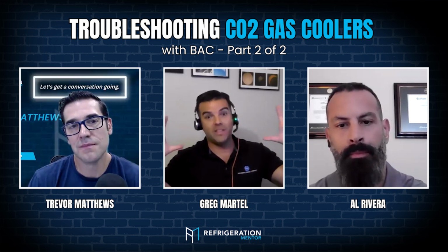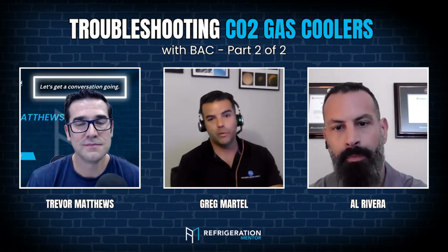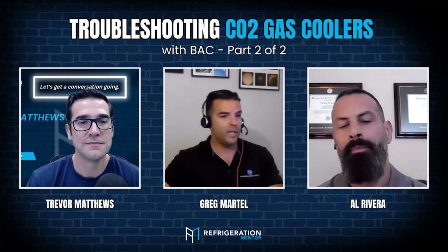It depends on what the customer wants to do. Another thing to keep in mind is that EC motors are highly efficient. They barely use any power. So sometimes running the fan at full speed, like some of our customers do, is actually more cost efficient, because remember the main thing that consumes power in the system is the compressor, right? So you're trying to keep your compressors happy. Sometimes it's cheaper just to run the condenser at full blast all year long, as long as you keep your head pressures down, and then you're saving money on your compressor side.